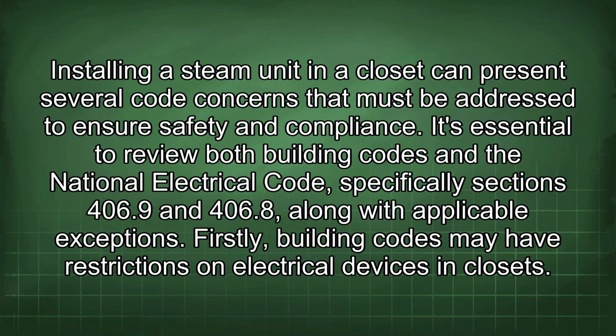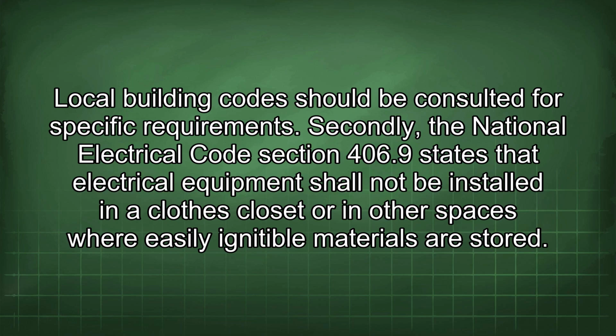Installing a steam unit in a closet can present several code concerns that must be addressed to ensure safety and compliance. It's essential to review both building codes and the National Electrical Code, specifically sections 406.9 and 406.8, along with applicable exceptions. Firstly, building codes may have restrictions on electrical devices in closets. Local building code should be consulted for specific requirements.